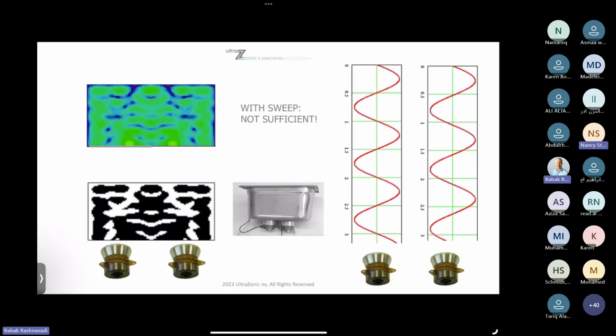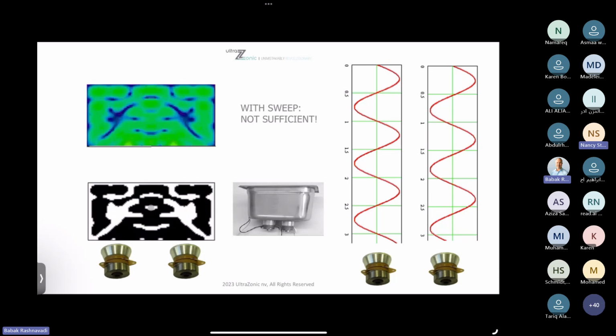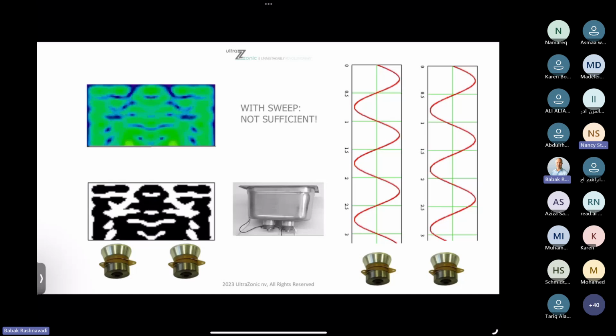What we see here in the middle is the same ultrasonic sink with two transducers. On the left side, we wanted to show that when creating cavitation in your sink, you still have open gaps. If you click on that, Babak, it should move a little. You see those two transducers are not creating the same cavitation bubbles everywhere, because the transducers are creating a standing wave, and a standing wave always creates the same frequencies and cavitation in the same spot in your ultrasonic device.